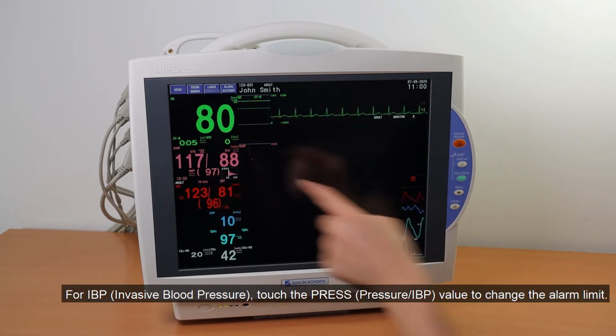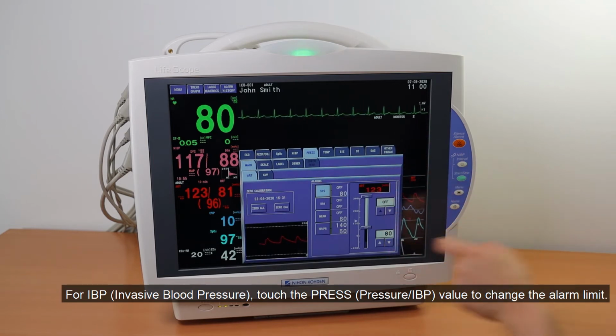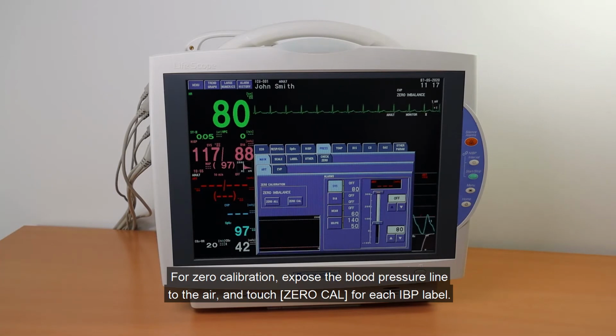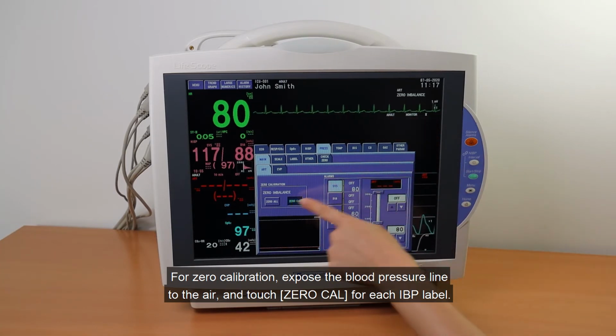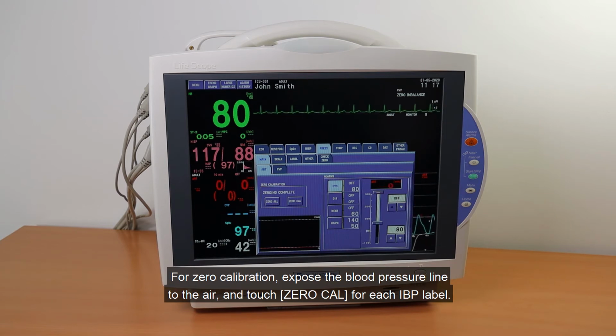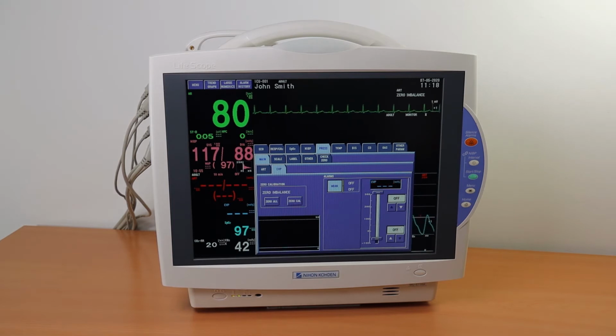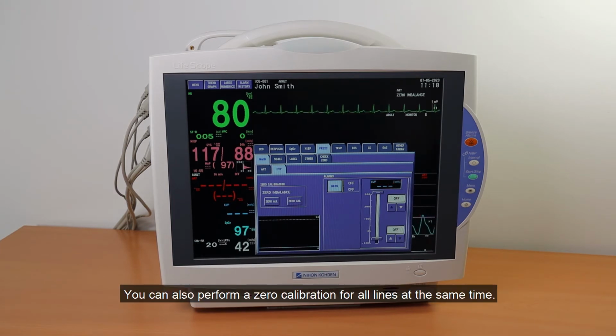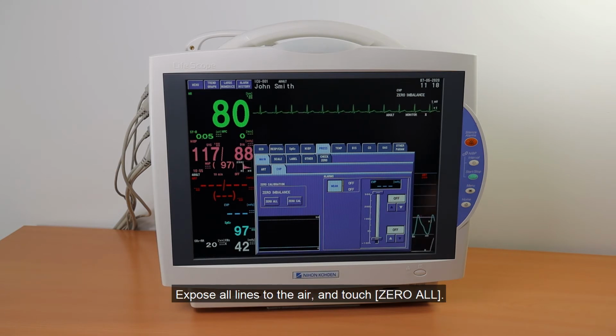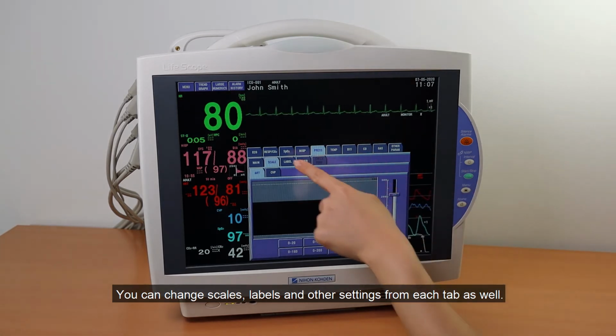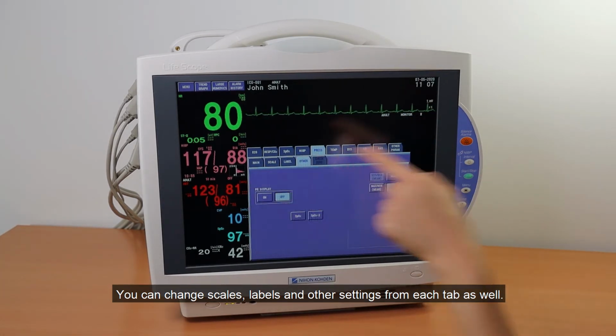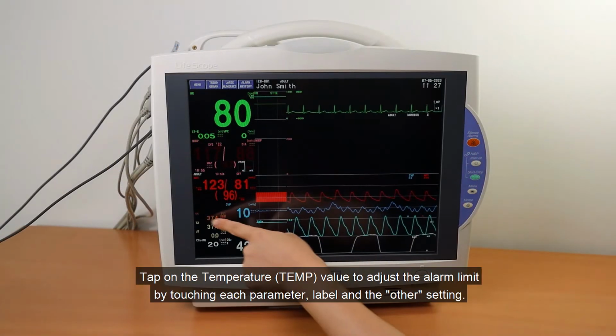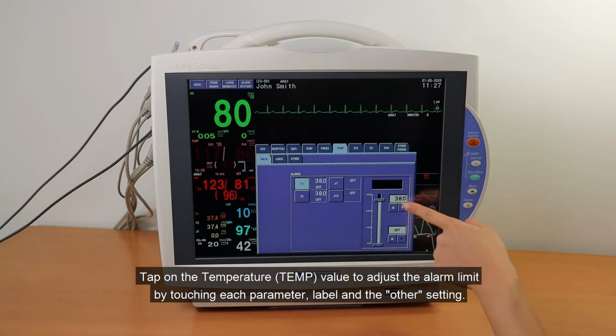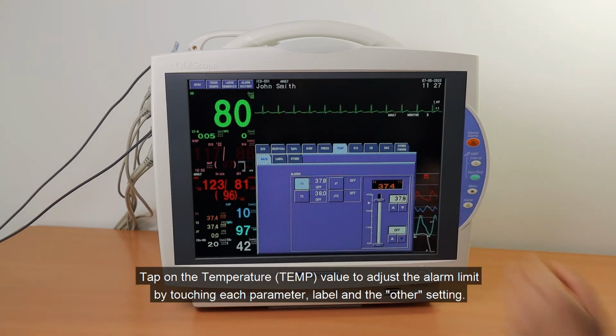For IBP, touch the pressure value to change the alarm limit. For zero calibration, expose the blood pressure line to the air and touch 0 cal for each IBP label. You can also perform a zero calibration for all lines at the same time. Expose all lines to the air and touch 0 all. You can change scales, labels, and other settings from each tab as well. Tap on the temperature value to adjust the alarm limit by touching each parameter, label, and the other setting.